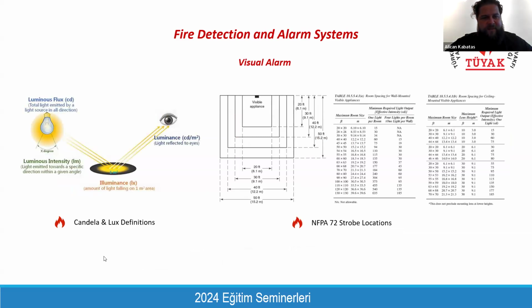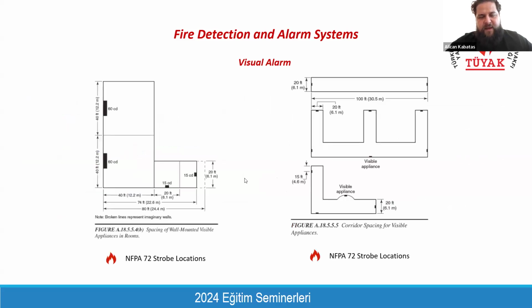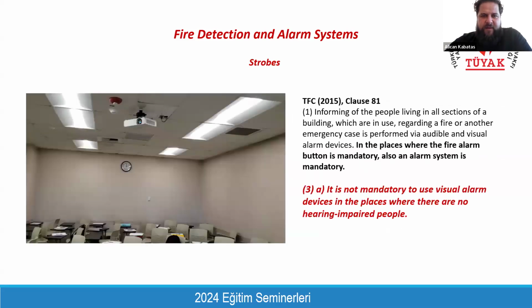For these visual alarms, we are checking the light intensity, so that even if you cannot hear the voice alarm, because you are disabled, or you wear headphones, or some noise-canceling earphones, you can see the visual alarm. And the spacing of these strobes is defined and determined according to this light intensity. And you can see some tables to define the spacing of the strobes. It means when we are locating these strobes, flashers, these are referenced from standards and calculations, as you can see.